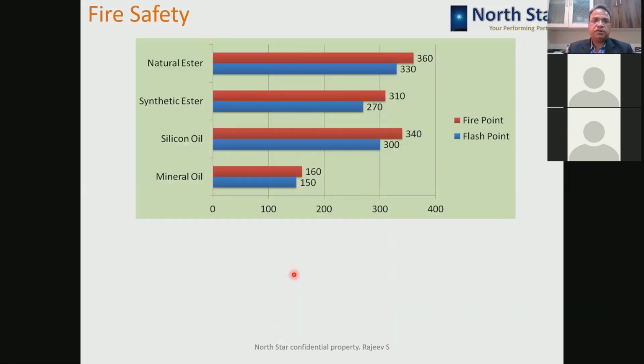Again, another depiction of fire safety. If you see here, fire point and flash point comparison, mineral oil has a flash point of 150 and fire point of 160. Silicon oil is better than this, which has 300 and 340 respectively. Synthetic esters is 270 flash point and fire point 310, and natural esters is best as far as fire point is concerned, 360, and flash point as 330. So if fire safety is concerned, natural esters are best suited.